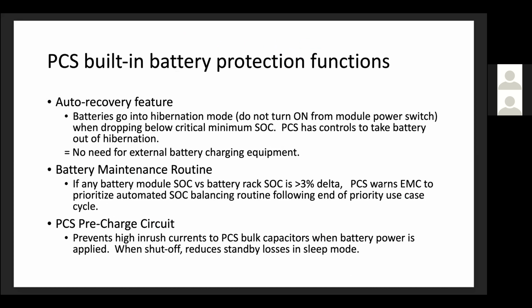Okay, quick look at some PCS built-in battery protection functions. The auto recovery feature: the batteries will go into a hibernation mode whenever they drop below a critical minimum SOC. If this does happen and you're on site as an installer, do not turn on the battery modules from the module power switch, because the PCS has controls to take that battery out of hibernation as long as there is grid voltage available. There's no need for external battery charging equipment, as I mentioned earlier in the presentation. There is, of course, a battery maintenance routine that's pretty standard for most systems. If any battery module SOC versus a battery rack SOC is greater than a 3% delta, the PCS will warn the controller to prioritize an automated SOC balancing routine following the end of the prior use case cycle, like charge or discharge because of PV.